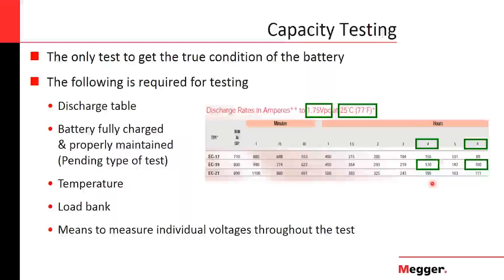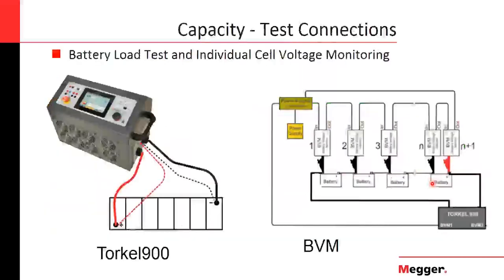This is how a typical connection will look like. So there's the battery here. You have your positive and negative posts, and you connect the load bank with the brains in it to be able to control the test. You program those parameters obtained from the table before, and you start running the test and just wait for the time to reach the 8 hours or the 4 hours that you selected, and you're looking for the battery to be able to deliver current during that amount of time.